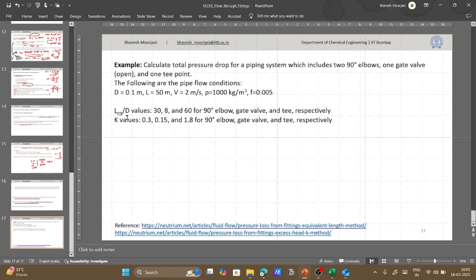So if you want to try it out, calculate the total pressure drop in a pipe system which has two 90-degree elbows, one gate valve and one T point, right? The pipe flow condition is given, and we know the L equivalent and the K value is given. So first we will try out with the L equivalent method.